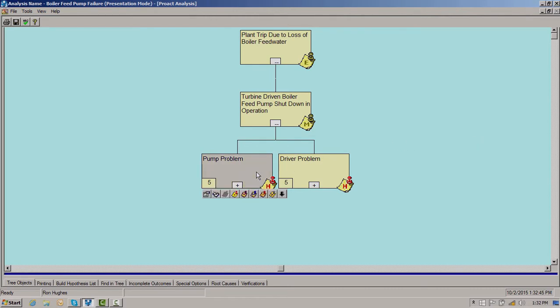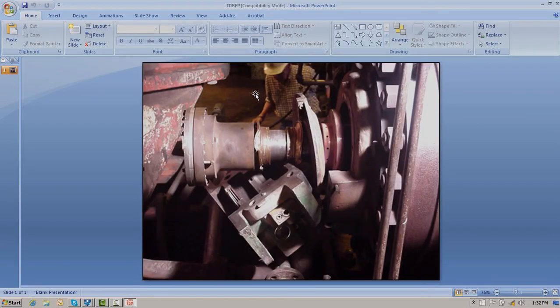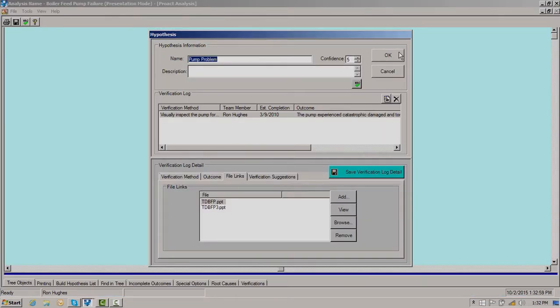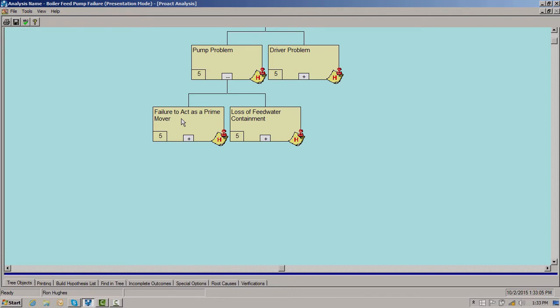Obviously we have a pump problem — you can see that from the picture I've already shown you, and you can tell the size of the equipment by the millwright standing next to it. The visual inspection proves we have a pump problem. Now we review PI data, and of course PI data shows where it shut down, but it also reveals that the pump was operating within normal design parameters at the time of the incident under investigation.